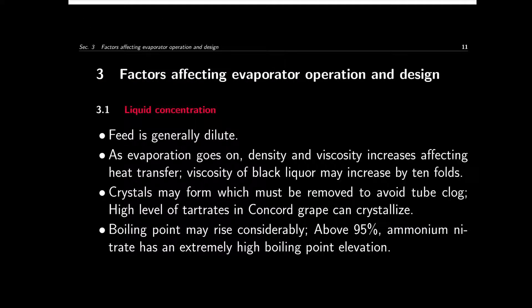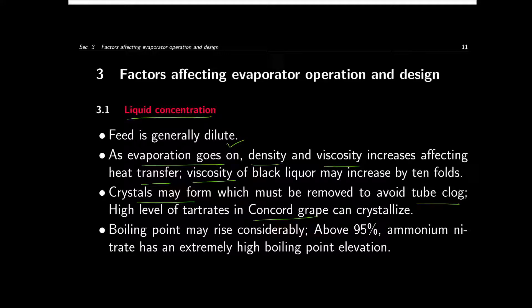Now let's look at the factors that affect the operation and design of an evaporator. Liquid concentration is one such factor — feed is generally dilute for an evaporator, but as evaporation goes on, both density and viscosity increase. These two parameters significantly affect heat transfer. For some cases, for example for the black liquor, the viscosity may increase by even 10 folds. Also with concentration increase, crystals may form which must be removed to avoid tube clogging in the evaporator. For example, for concord grape, the high level of tartarates can crystallize.